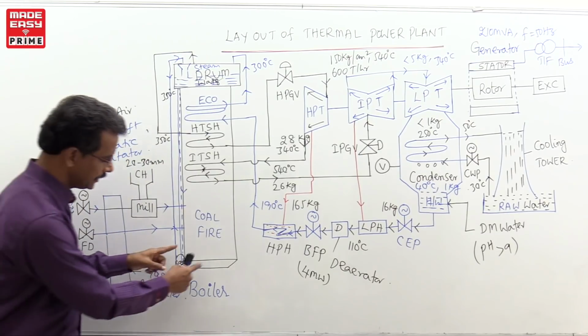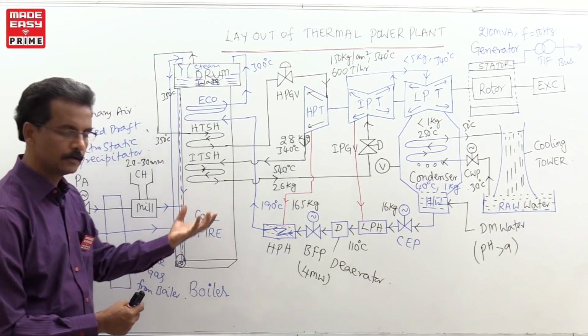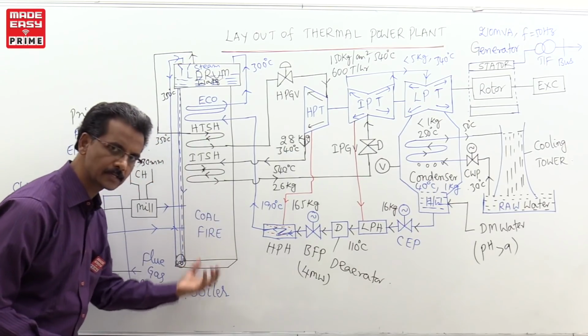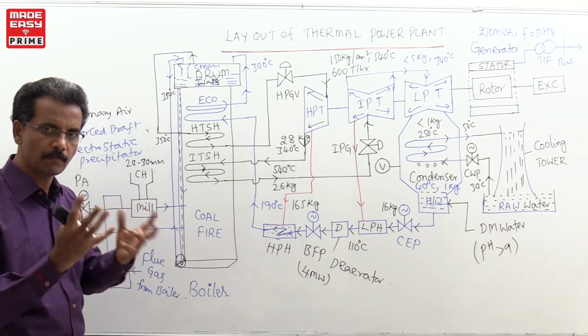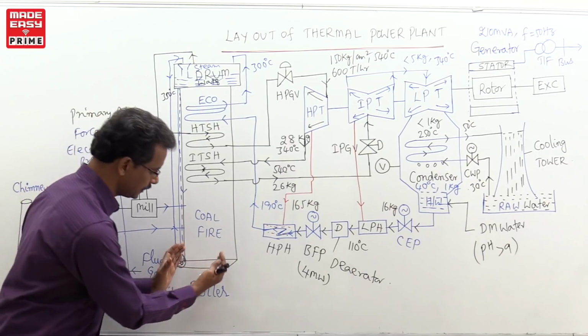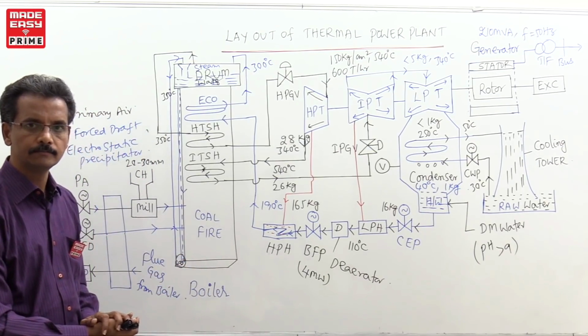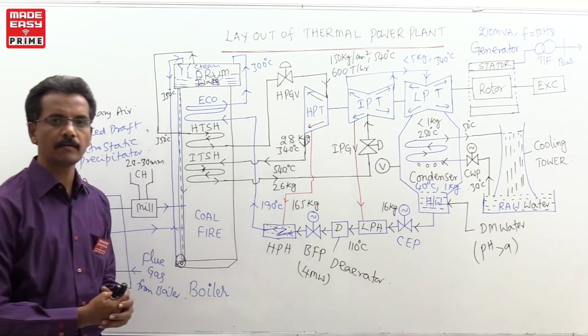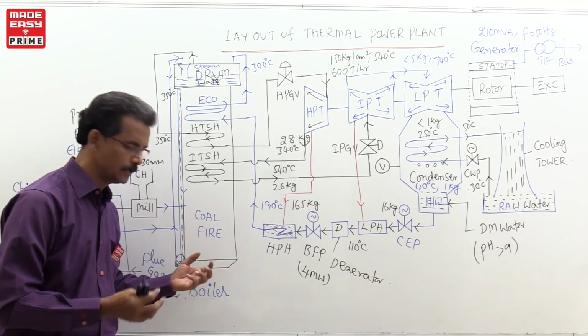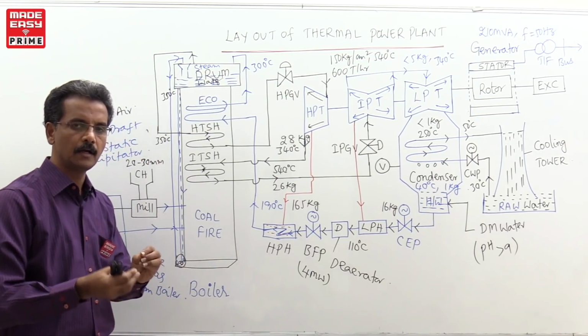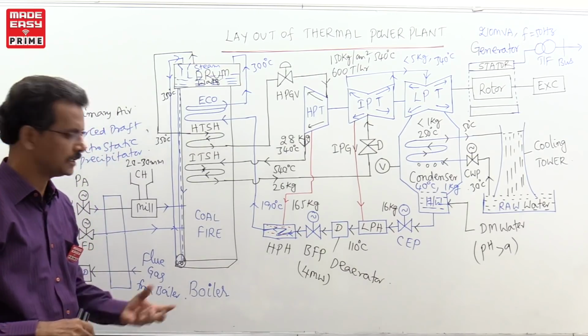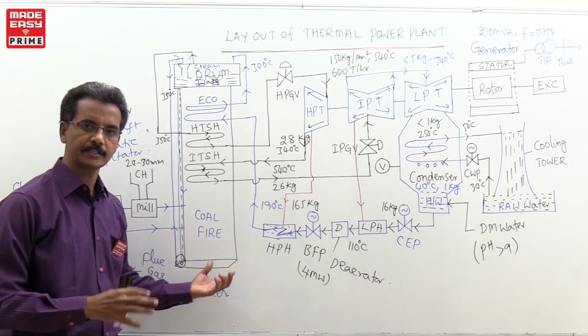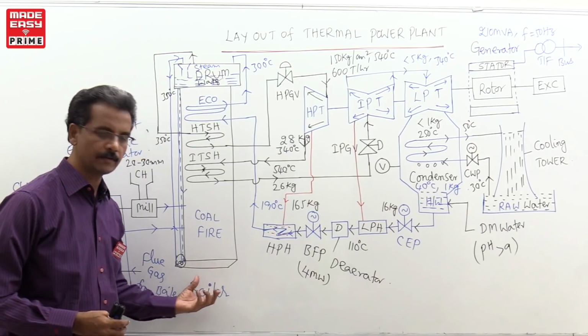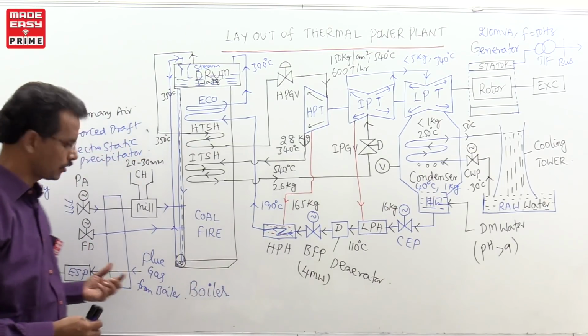The other is this. Here, the coal is fired in the boiler, and some ash particles, not a huge quantity, a small quantity, are collected at the bottom of the boiler. Clear? Whatever ash falls at the bottom of the boiler should also be collected, mixed with water and dumped into the ash pond. That is what is called the bottom ash hopper. This provides the bottom ash collection.